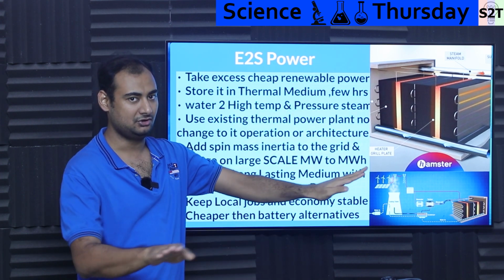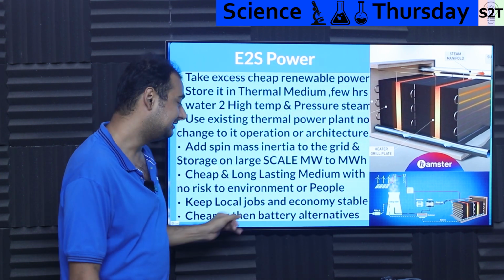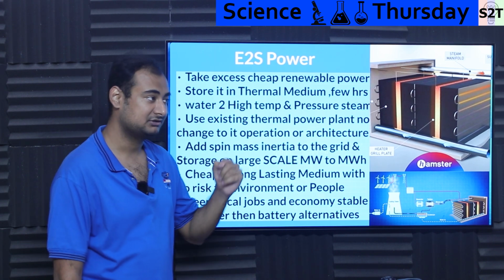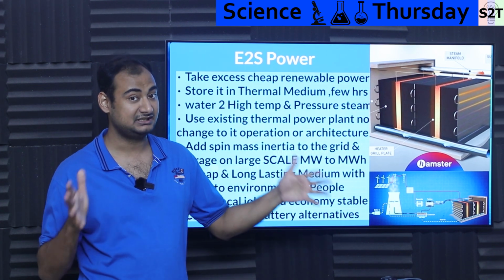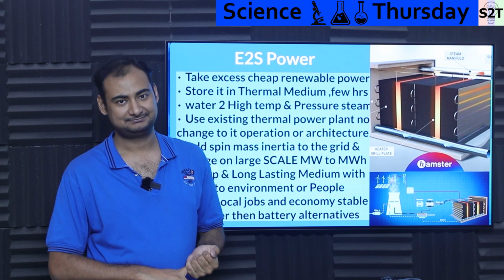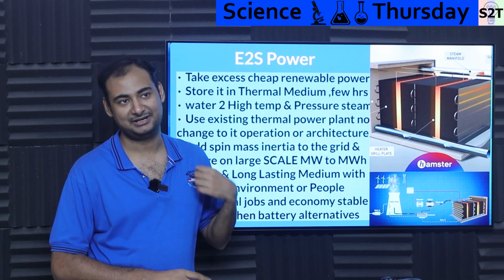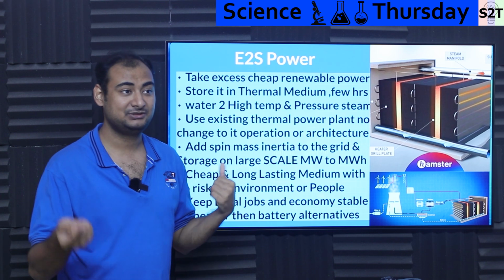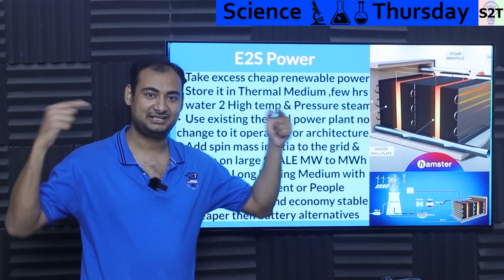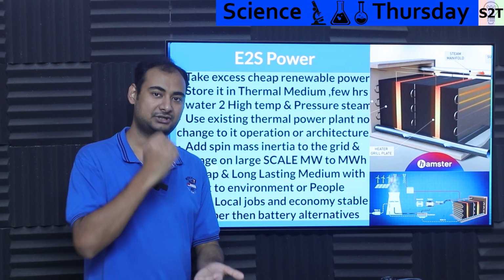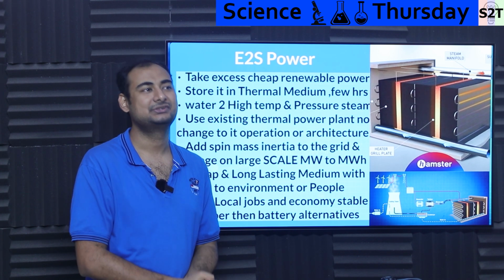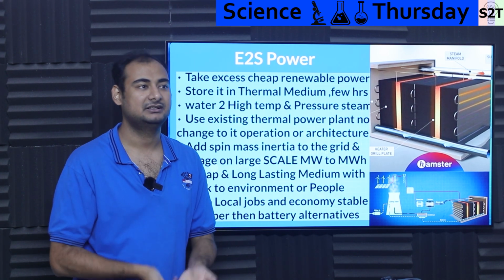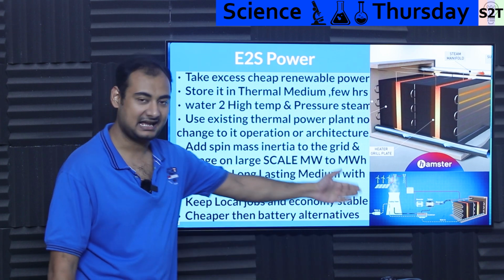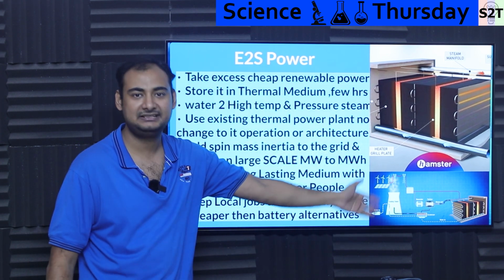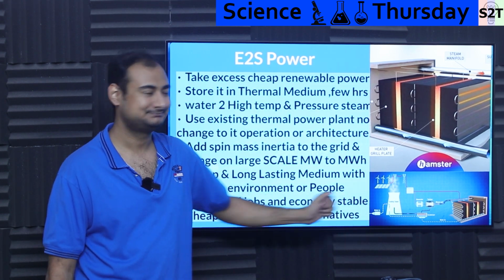Instead you convert it, and it's cheaper than battery alternatives, not only because you can scale the megawatt-hours to very large scale, but it also gives you inertia. You cannot get inertia with a battery system. You can program the inverter to not take signal from the outside, have an atomic clock there so it acts as the source, but it doesn't have that physical reliability. This has the physical reliability.